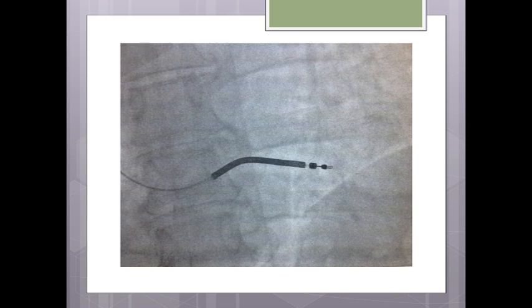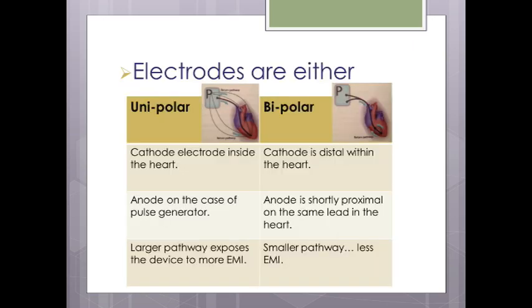Electrodes are either unipolar or bipolar. In unipolar configuration, the cathode is the electrode embedded inside the heart while the anode is the generator casing, usually at the pectoral region — a large area for electricity to traverse. In bipolar, cathode and anode are on the same lead, both inside the heart, so electricity does not leave the heart. This is important because electromagnetic interference is more common with unipolar than bipolar.